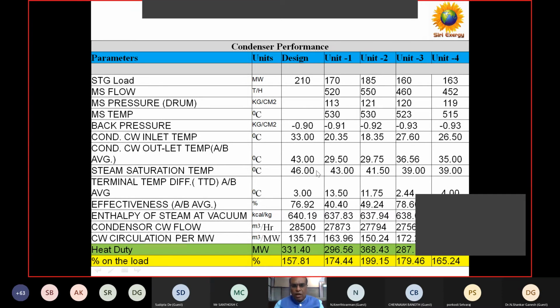So this is the overall plant, 210. So what is the input? Input, again, I am giving: one pit is around 147 tons of coal, your consumption will be 161 tons per hour. So the heat rate is about the gross calorific value and heat input. Converted into megawatts, it will be 600. Though you want to produce only 210 megawatt, the actual heat input is almost 600 megawatt. So 600 we are giving as input. Finally we are getting only 210 megawatt.